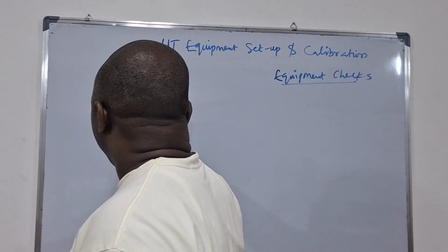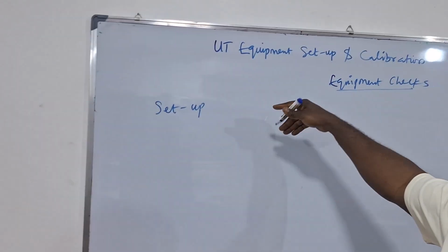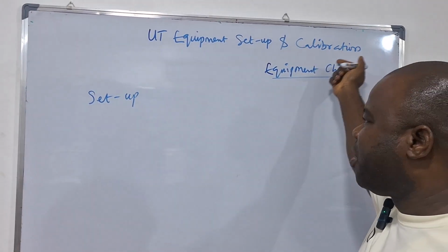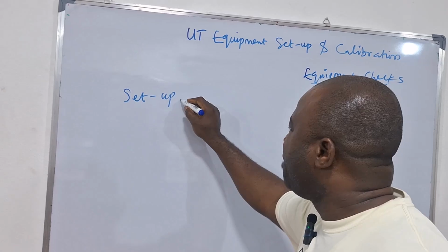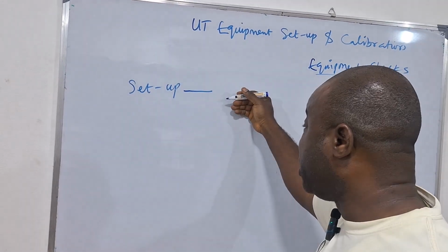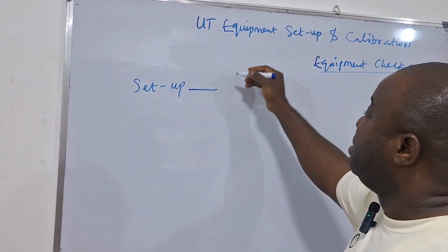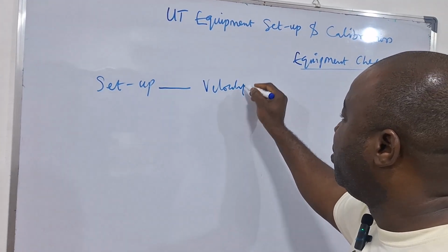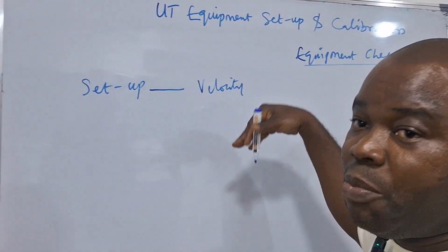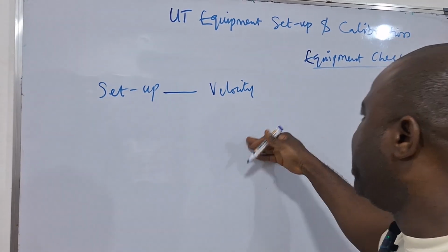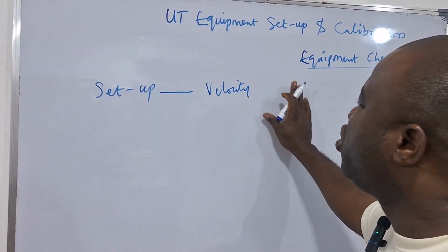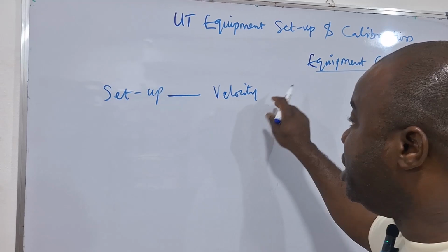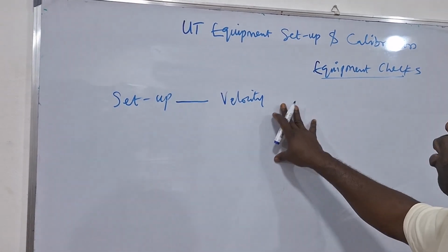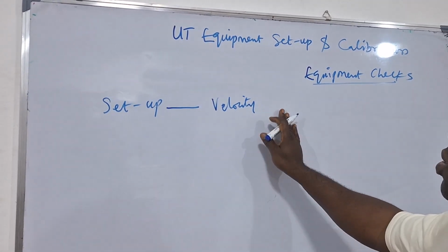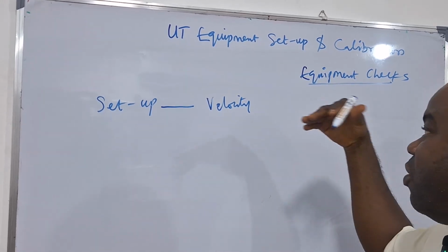So the first one is setup. In the true sense of it, setup does not really require you to perform any form of calibration. So what you are basically doing when you are setting up your UT equipment, you are entering your parameters. This could be your velocity, your probe type, your probe angle, your index points, and those essential values that you need for your UT machine to work properly. So setup may be dependent on the kind of machine you are using.